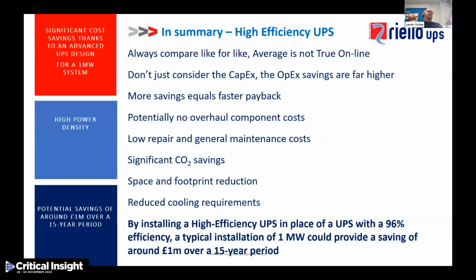So what can we say in summary? Always compare like for like. Average is not a true online figure, so always read between the lines. Don't just consider the CapEx. Look at the OpEx savings, as these are far higher. More savings equals a faster payback. These can all be calculated based upon a specific application. We've got significantly lower repair and general maintenance costs, significant CO2 savings, a smaller space requirement and footprint, and reduced cooling requirements. So basically, by installing a high efficiency UPS in place of a UPS with, say, 96% efficiency, a typical installation of 1 megawatt could provide a saving of around £1 million over 15 years.